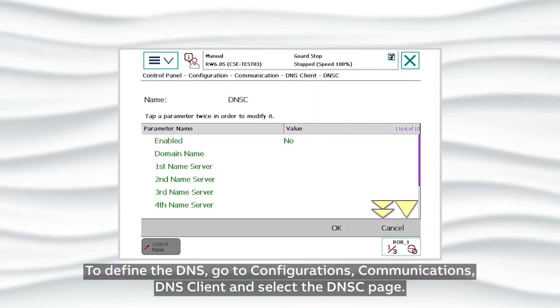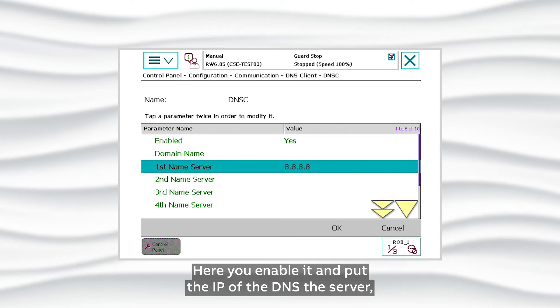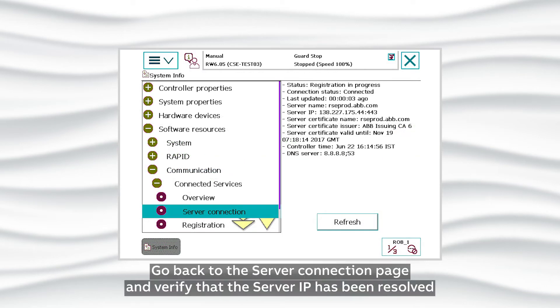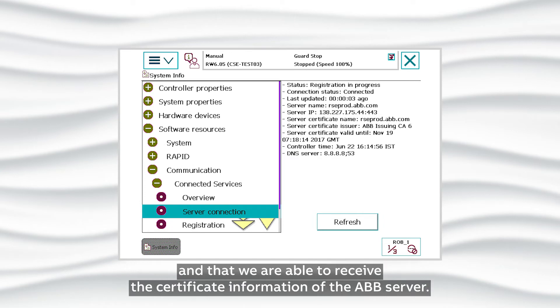To define the DNS, go to Configurations, Communications, DNS Client and select the DNS Client page. Here you enable it and put the IP of the DNS server, in this case 8.8.8.8. Go back to the Server Connection page and verify that the server IP has been resolved and that we are able to receive the certificate information of the ABB Server.